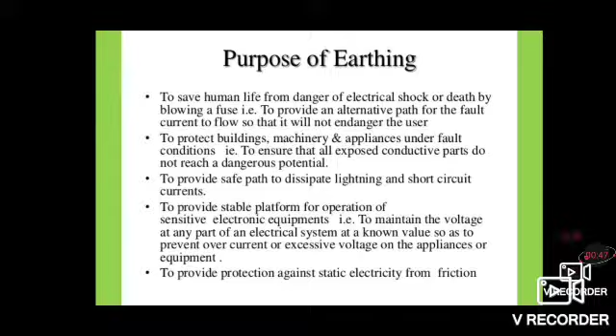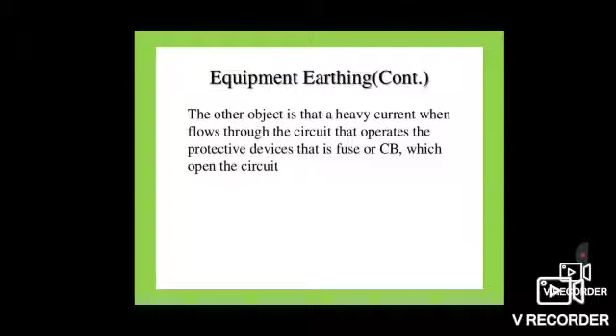Equipment earthing. In case of insulation failure, the primary objective of connecting all the above points and apparatus to earth is to release the charge accumulated on them immediately to earth so that the person coming in contact may not experience an electric shock. The other objective is that a heavy current flows through the circuit that operates the protective devices, that is the fuse or circuit breaker, which opens the circuit.